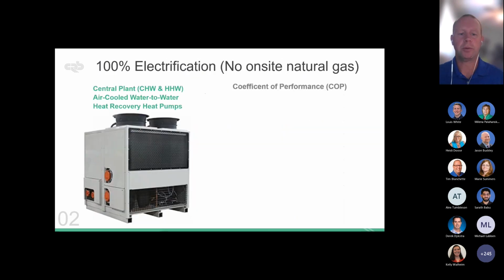For this client, we evaluated a few different mechanical approaches. We ended up going with this air-cooled, water heat pump, heat recovery heat pump - that's a mouthful. What you're seeing looks like a modular chiller, like a 60-ton modular chiller, which effectively it is. But you're seeing 4 pipes: 2 chilled water, 2 hot. What's great about that is it's very efficient.